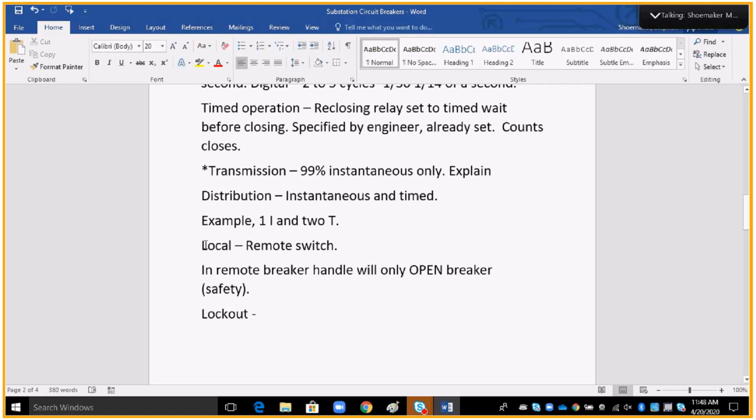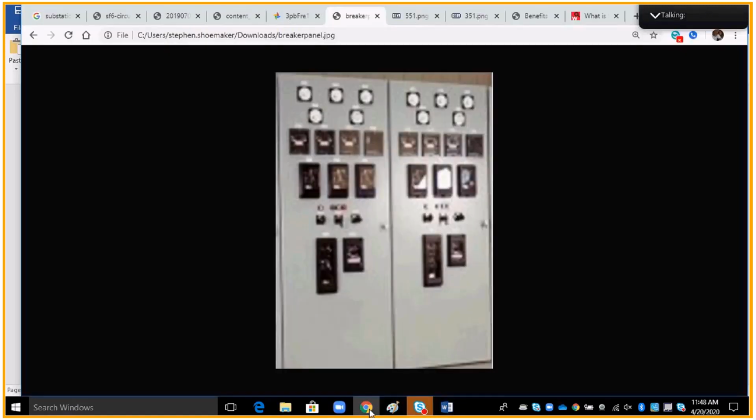All right, on the breaker itself, it has a local and remote switch. Let me go back to that. So we talked pretty much about the relays, 1, 2, 3, 4, and 5: phase relays, ground relays, reclosing relay. Not worried about this section up here yet. The open and close handle with the lights, green, white, and red, you've got on this side, and they're labeled for you. We're going to use this side, a local remote, and what they call a tagging relay. Okay? Let's talk about the local remote first.